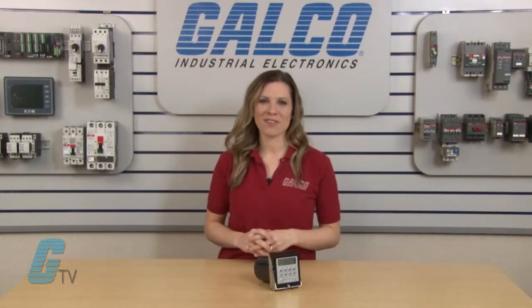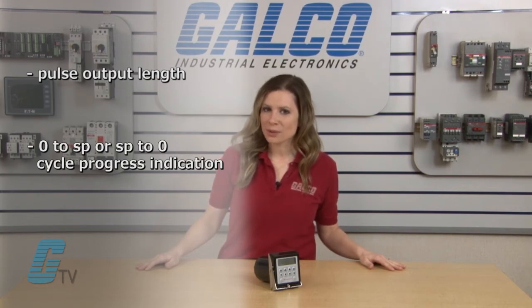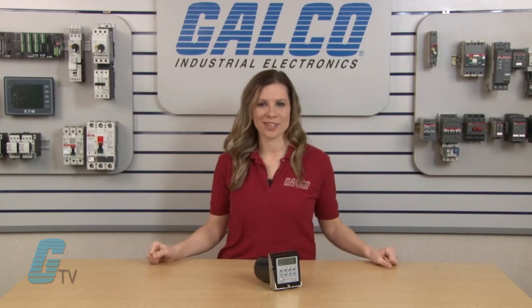These programmable functions control the pulse output length, set point to zero or zero to set point cycle progress indication, and count input scale factor. The keypad can also be locked to prevent unauthorized changes.